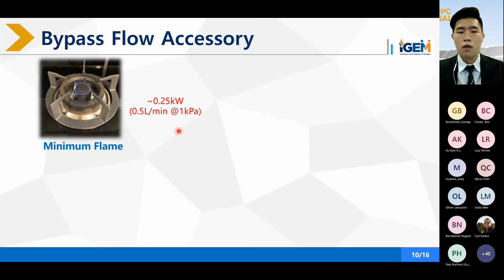I've done a simulation focusing on the minimum flame, which is only 0.25 kilowatt or 0.5 liter per minute at 1 kPa in terms of flow rate. And in the simulation, I found that the velocity above the sensor surface is 0, which you can see in this white region. That means the sensor actually senses nothing because there is no gas flowing above the sensor surface and no temperature difference set up between the two thermopiles.